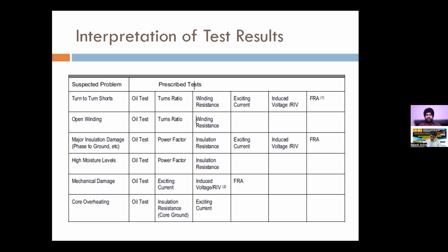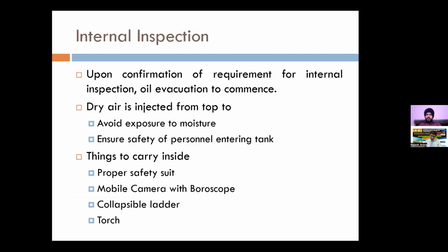And then if there is core overheating, then IR, core to ground mode, and excitation current will indicate the problems. Now that you have got a brief idea of the likely cause based on the LV test results, you need to confirm your hypothesis, and you need to carry out the internal inspection.